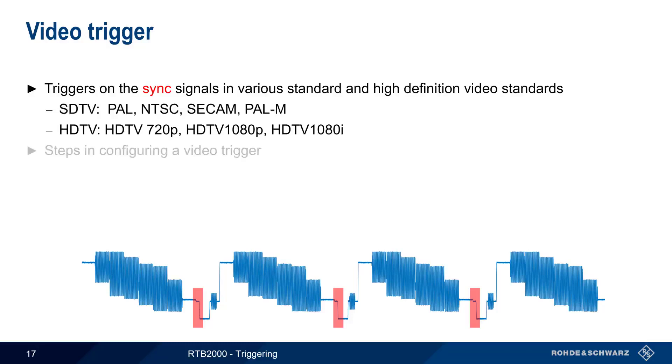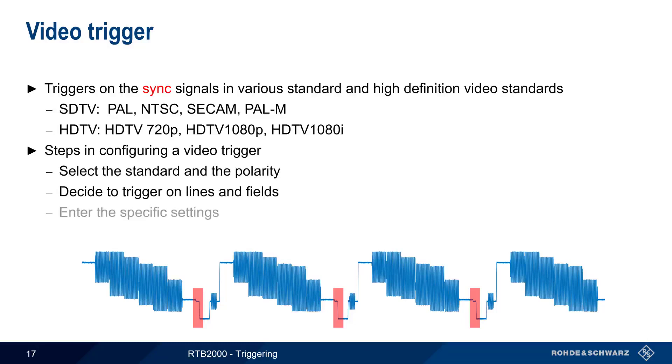Another somewhat less common trigger type is the video trigger. This type of trigger starts an acquisition on the sync signals or pulses, here shown in red, that are used to mark the start of each scan line in a video signal. The RTB supports a variety of both standard definition as well as high definition video formats. We won't be going into detail on these formats in this presentation. To configure a video trigger, three steps are required: selecting a video standard and the polarity, deciding which lines or fields to trigger on, and entering any specific settings. Let's take a look at an example.